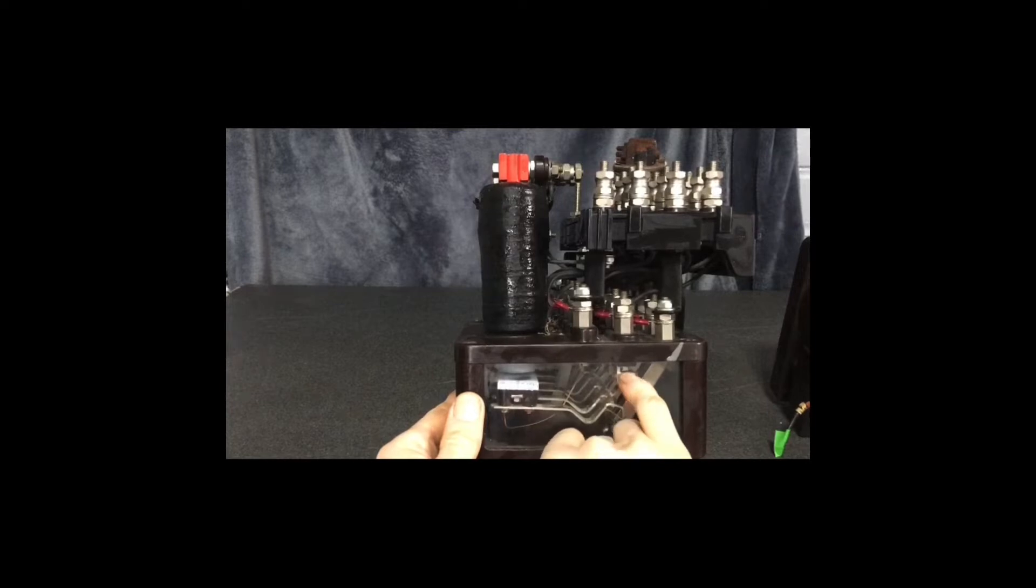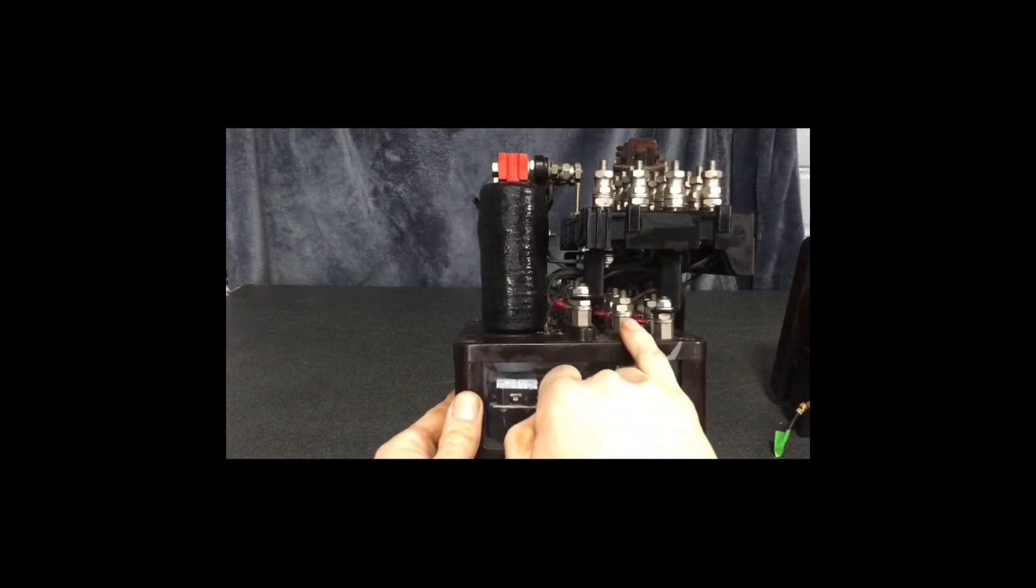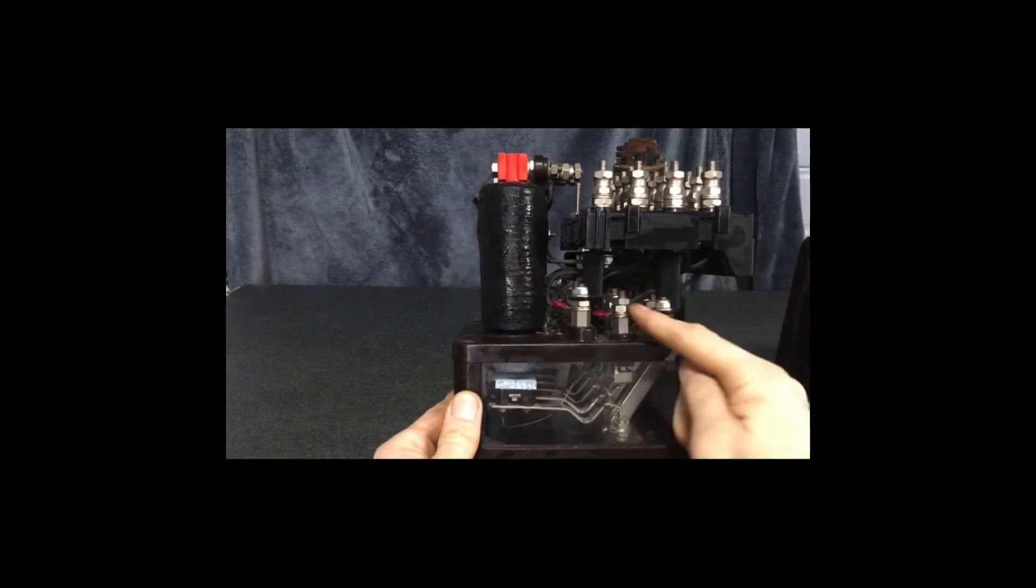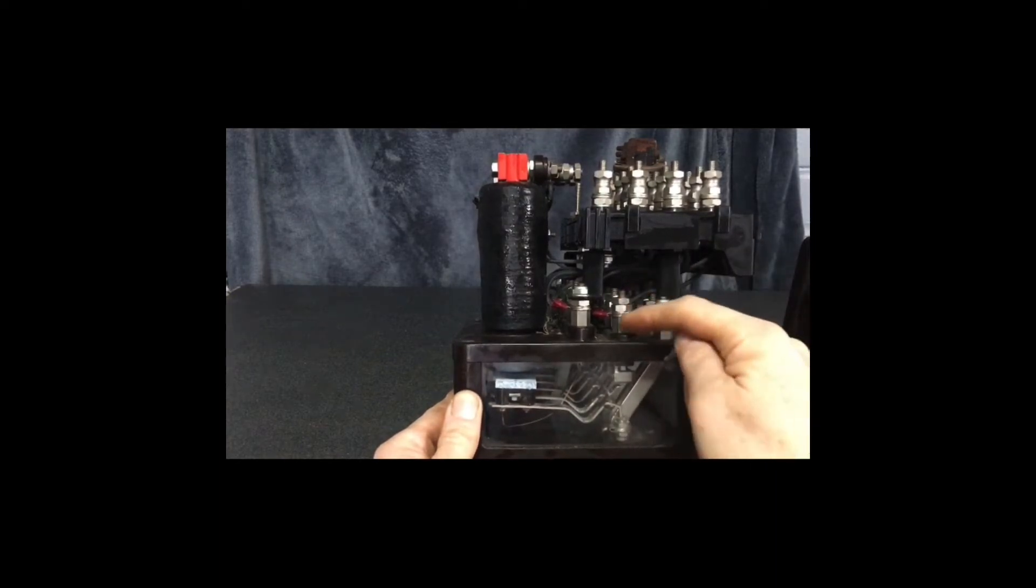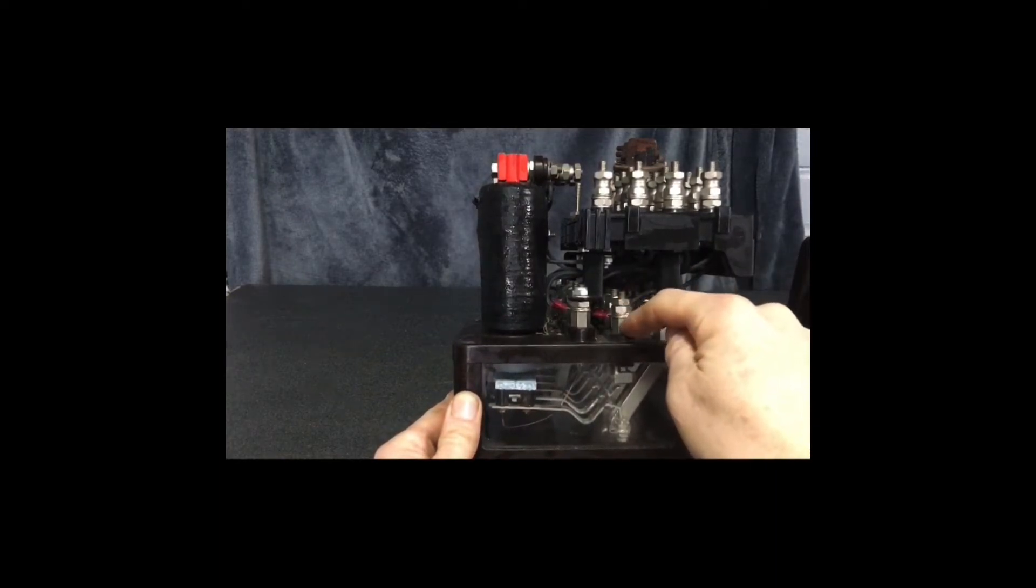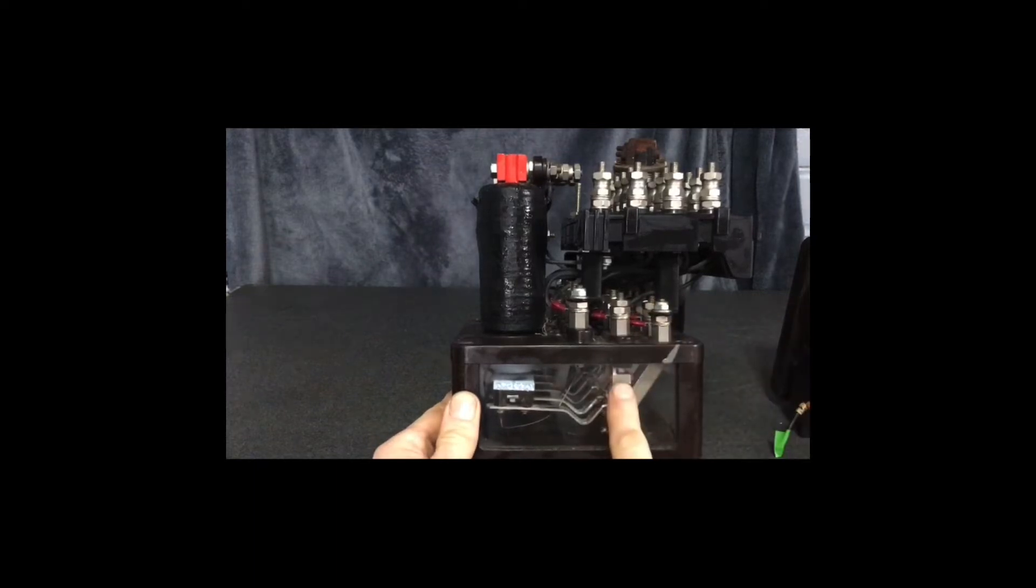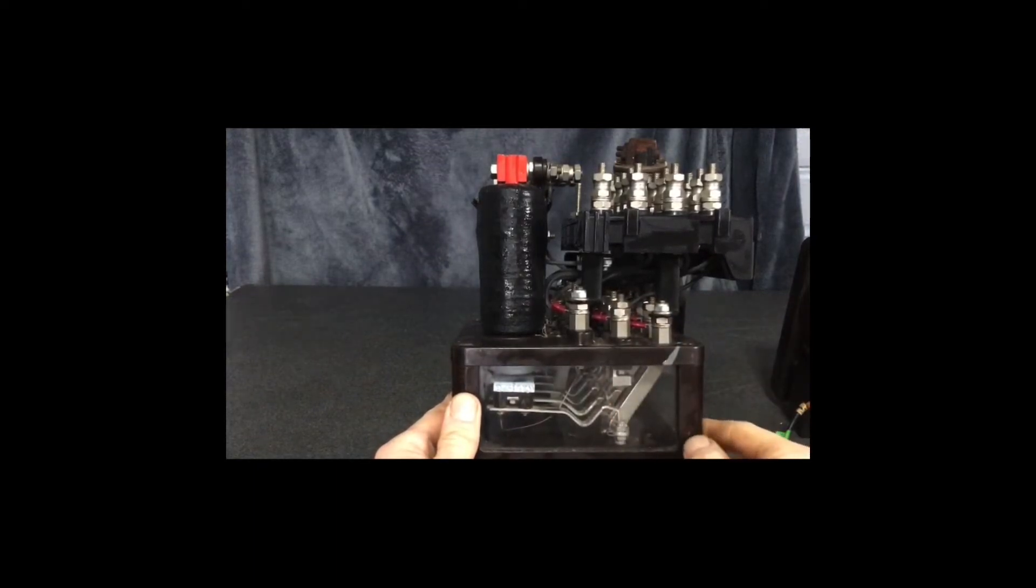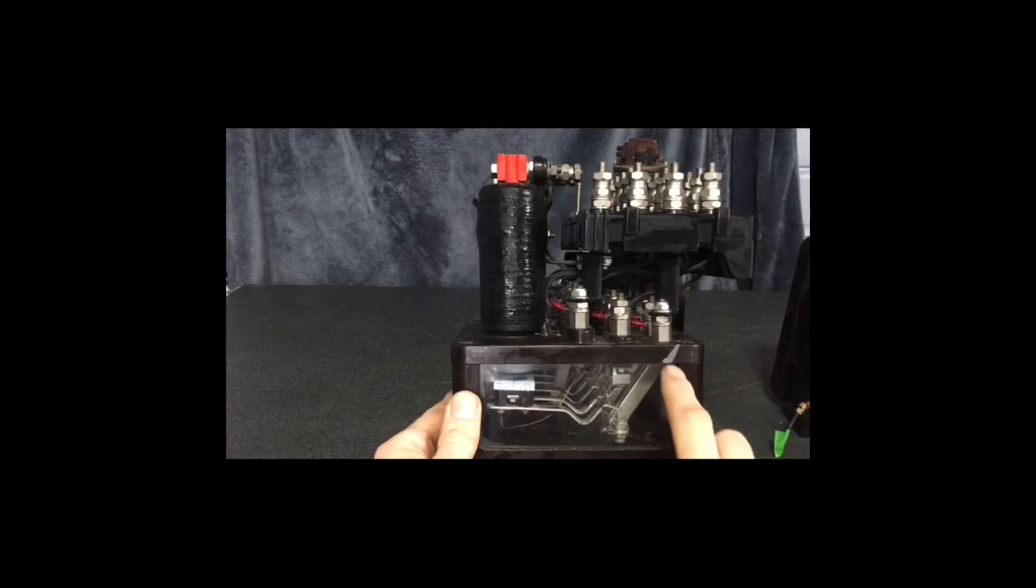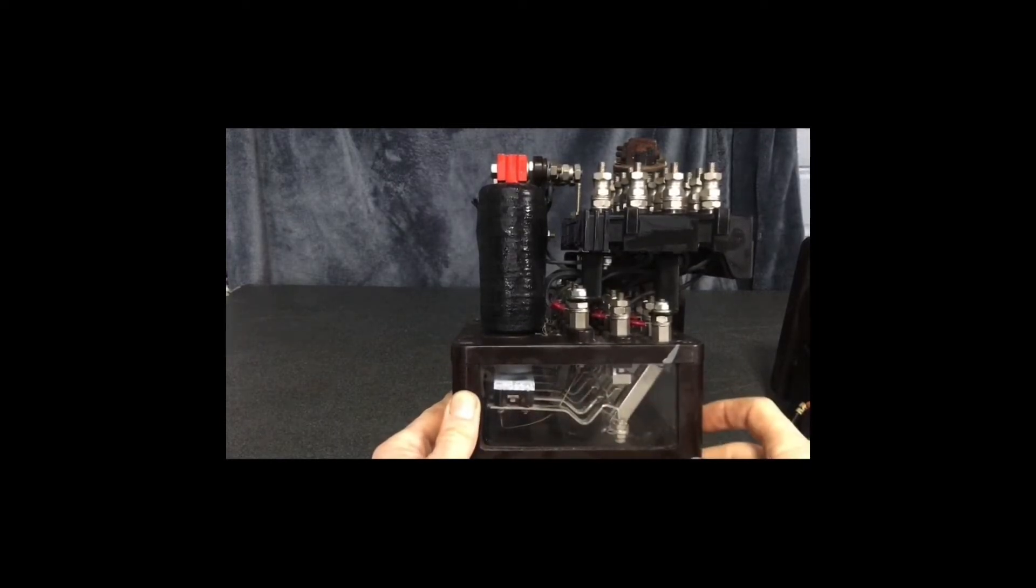That's the nut I was mentioning that has a tendency to shear off inside. It's a 2BA screw that goes up into this. These are recessed and they have known these in the past, when they snap off, they've been re-drilled, re-tapped in there, and a 2BA nut has been put back in there to repair it. That was the days of the past, but you can get these re-serviced at any of the major manufacturers.